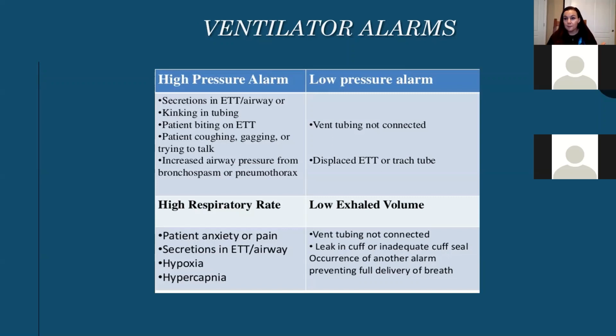Your low pressure alarm means that your vent is not connected or your ET tube's not in place. And if the vent tubing is not connected, you can then break that down into there's a crack in your circuit, there's a crack in your filter. I have an inspiratory and an expiratory line plus 2 lines that measure things at the ET tube. So there are 4 lengths of tubing that I have to check when I have a low pressure alarm, and I've determined, number 1, that my ET tube is still in.